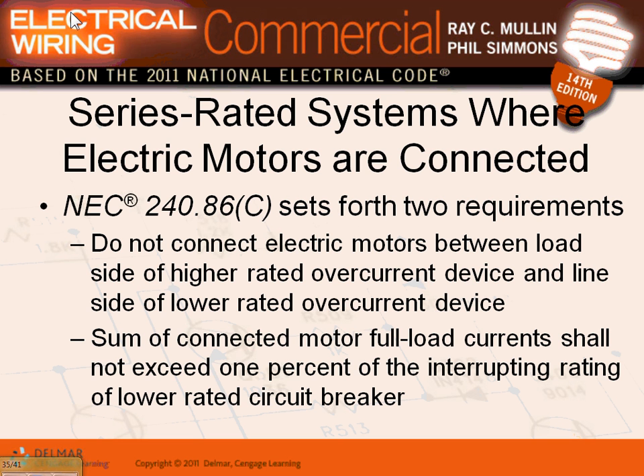Series rated motors: if you have motors, you can't use series rated. That's why, guys, if you remember when we talked about series rated, it's notoriously famous in two applications: lighting panels and receptacle panels. Most of the time, a panel like this feeds 90% lights. I can have a series rated 10K, and the feeder ahead of it could be 22K. If it's feeding machines, motors, anything motors, it's fully rated. If most of the equipment is feeding machines, you are fully rated.